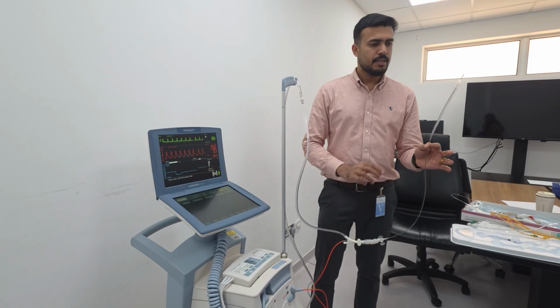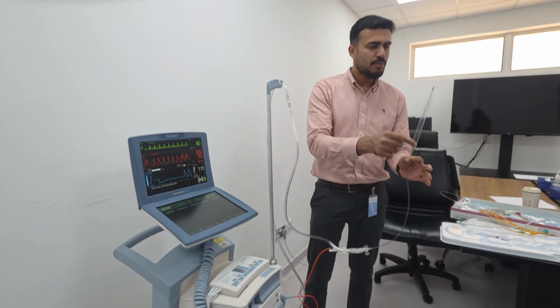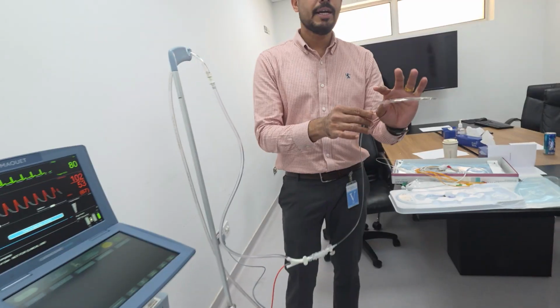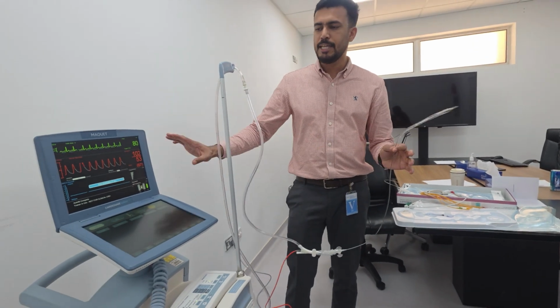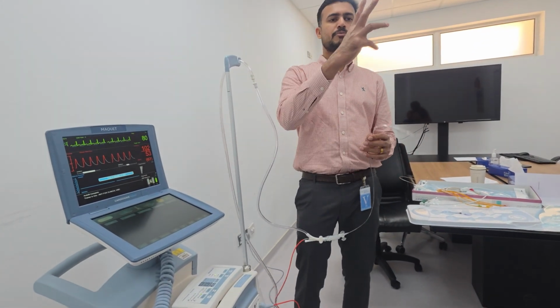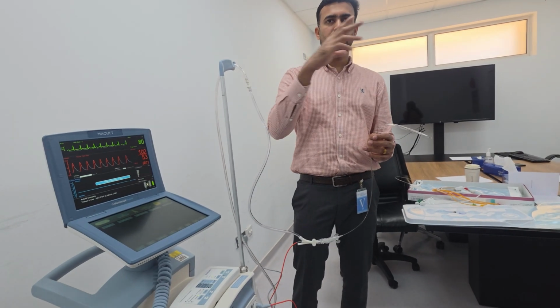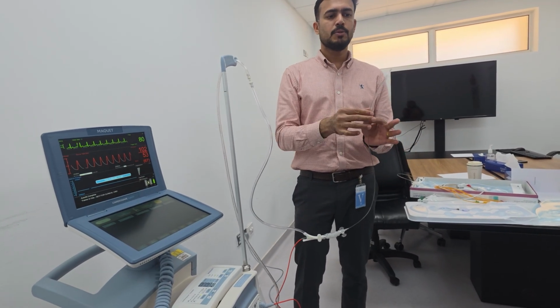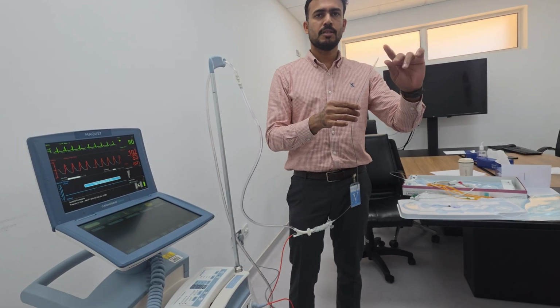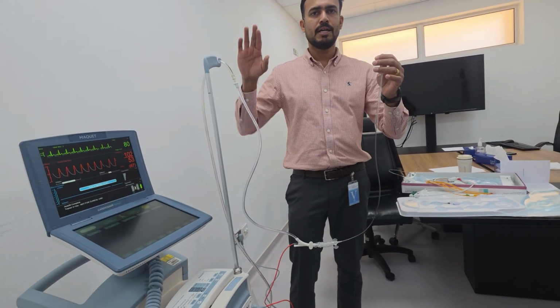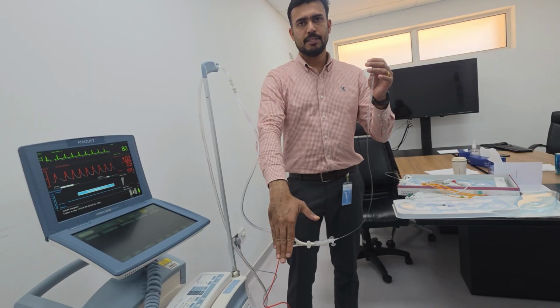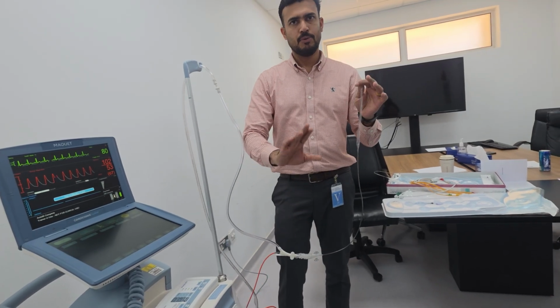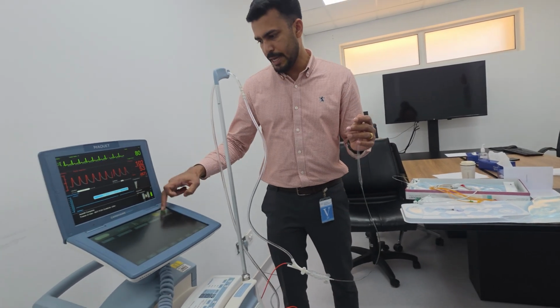Autofill complete. Start. Now it starts pumping. So the same helium will work for the next 2 hours. You have enough time. But if any technical issue happens to the machine, imagine the balloon was inflating and the machine shut down for any reason. It will never stay in the inflated position. If something happens, we have a safety valve. It will open here and the balloon will be deflated automatically. It's a safety feature. Don't worry about it. So autofill complete. I can start it.